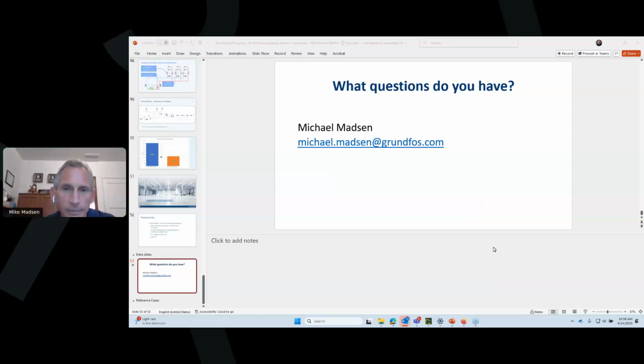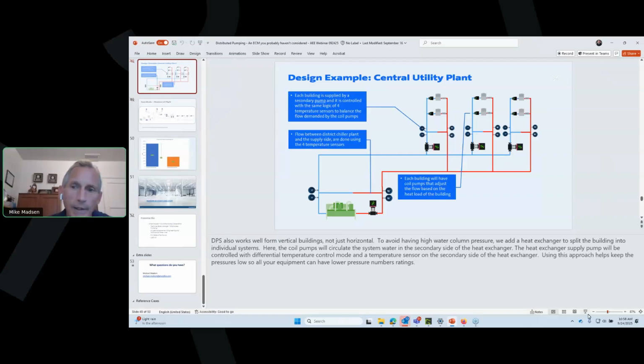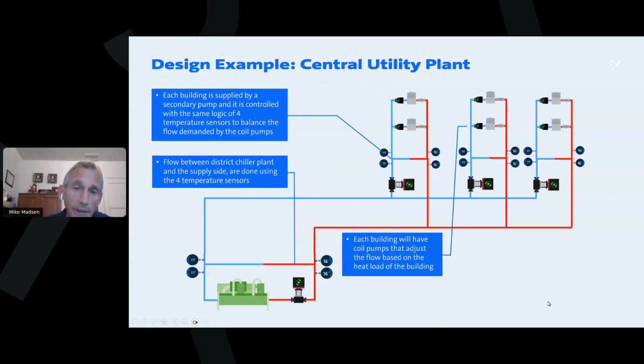Okay. For a campus with a central plant, can you do distributed pumping only on a few buildings at a time, rather than do you have to do the whole plant? You really need to do the whole plant. So sometimes if you get into a campus situation, the primary loop has heat exchangers on each building because they don't want the buildings mixing with the primary loop. If you have a heat exchanger, we can do buildings individually, one at a time.